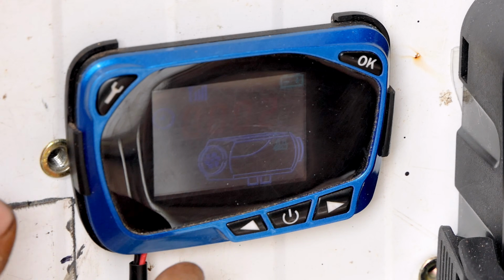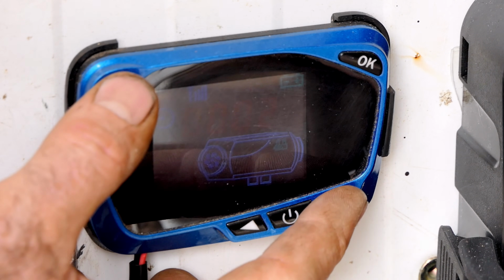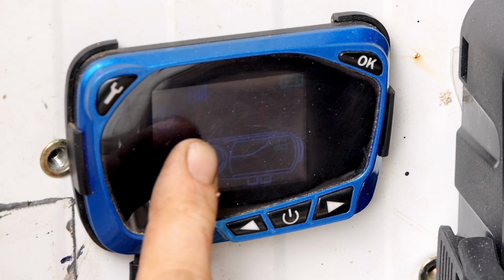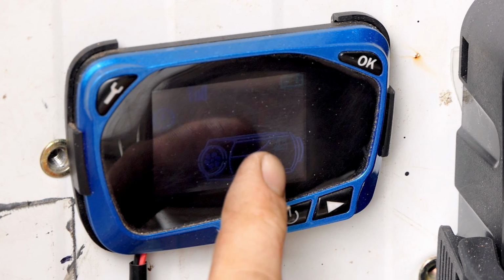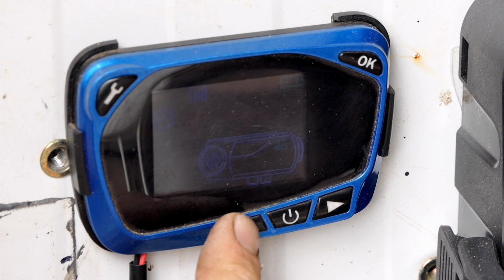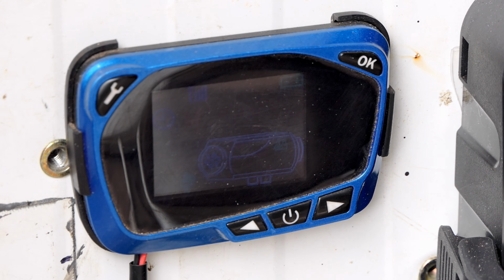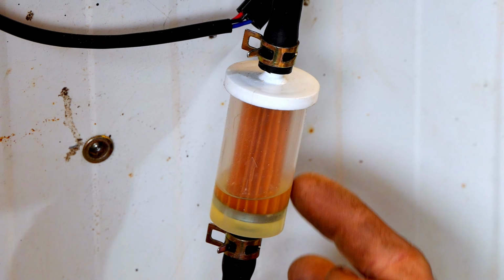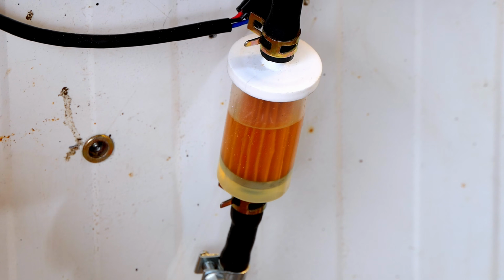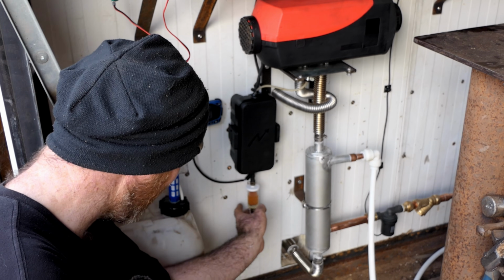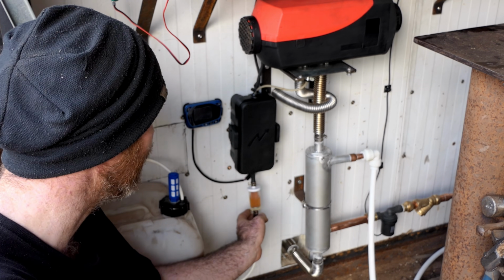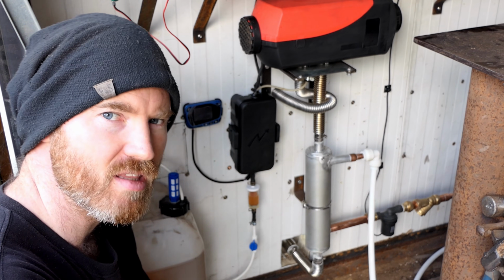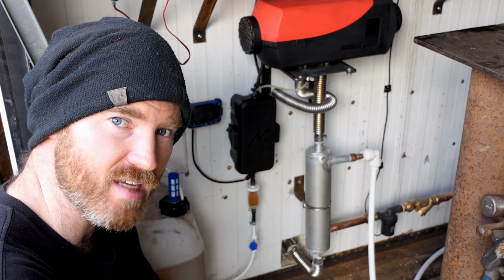Now on this particular controller, I'm going to press that button and that button at the same time, and immediately it says H off. I want to turn that to on - that's basically the pump for priming. There you go, it's slowly making its way up. Right, I've turned the pump off. I've still got a bit of an air bubble in the filter here, but I can see fuel is actually going into the main burner. So I think we're now ready for the test.